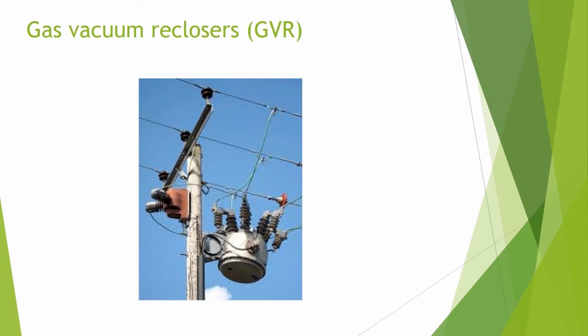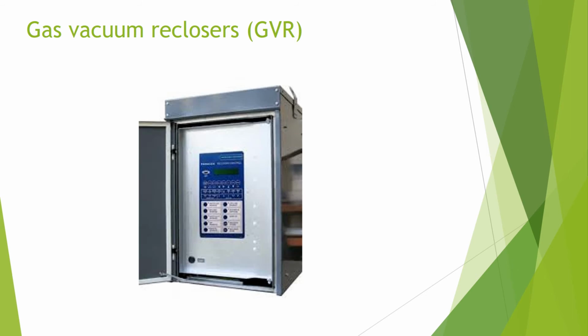Gas vacuum reclosers, GVRs. They are mounted under the overhead line they control. The GVR is a vacuum insulated circuit breaker housed within a tank filled with SF6 gas. They can be controlled locally via an electronic control panel or remotely via telecontrol. GVRs can be set up to carry out several protection functions and have many adjustable settings.